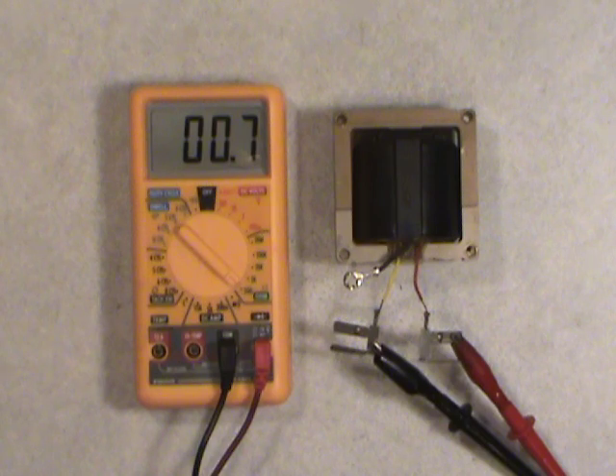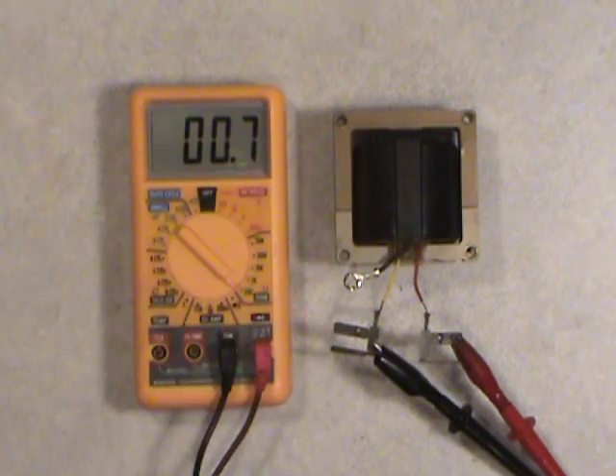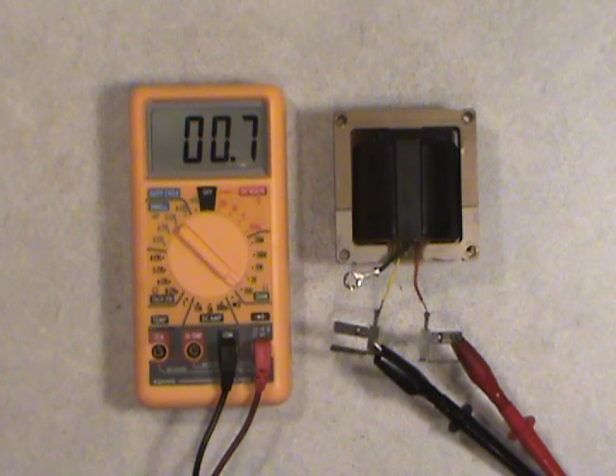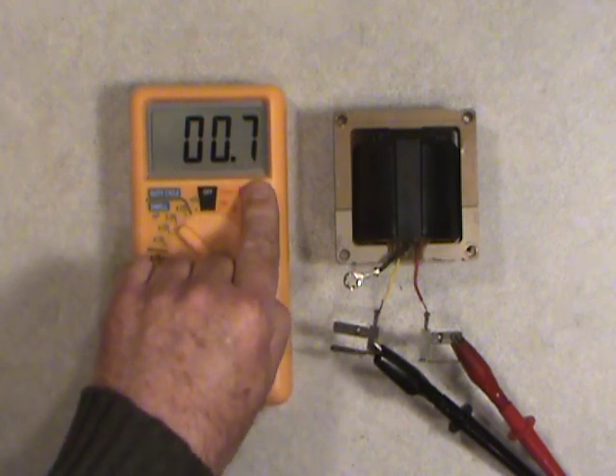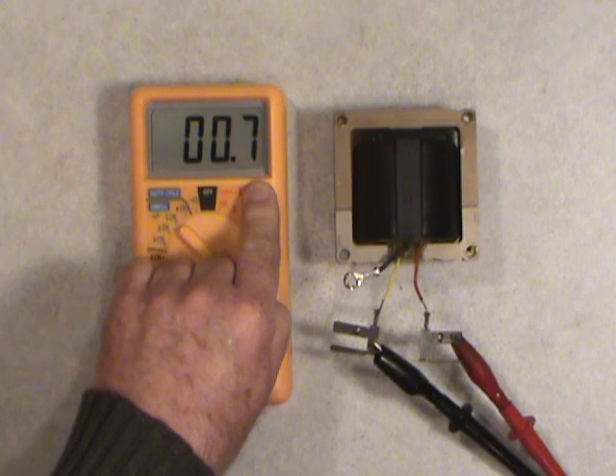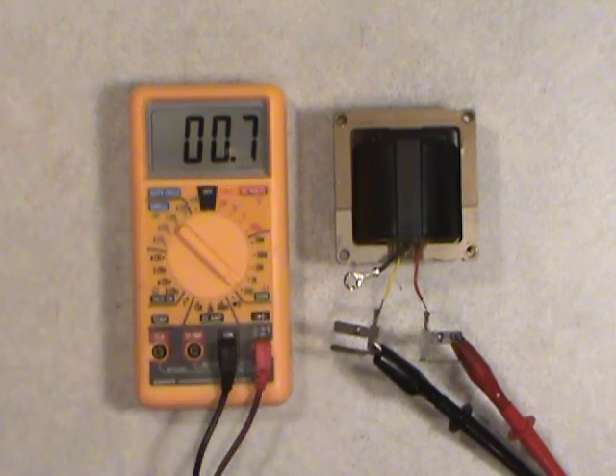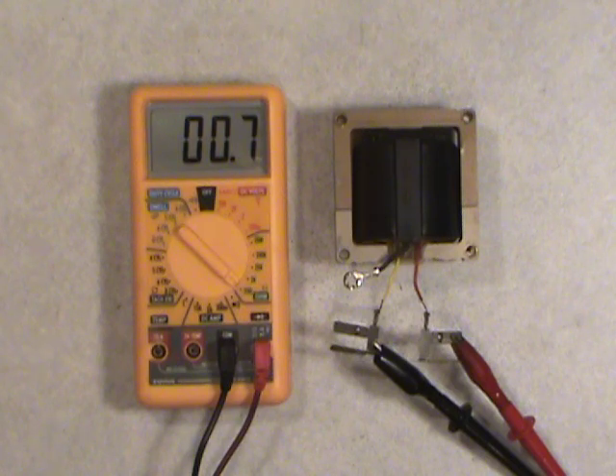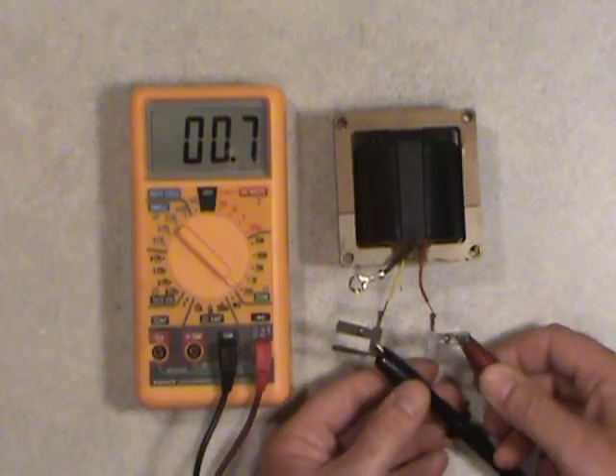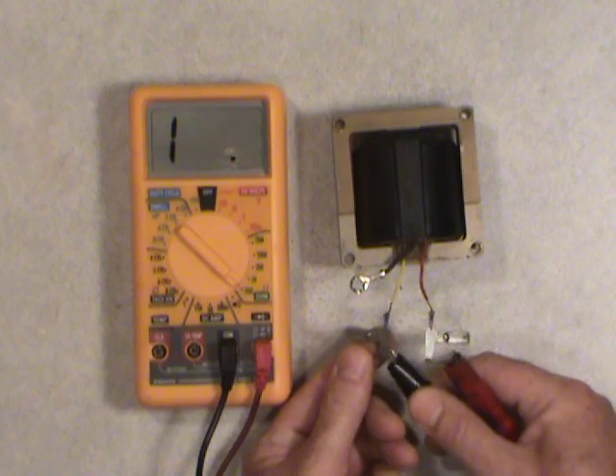Okay, so for the low, as long as you've got in general ballpark figures for low, as long as you're 1.0 or lower, meaning a full 1, as this is going to be 0.4 because of the difference in the calibration of the meter, we're well within range of from 0 to 1 ohm. So we're about halfway at 0.4. Remember, you have to subtract that 0.3. So our low end low ohm meter reading on the primary coil checks out.